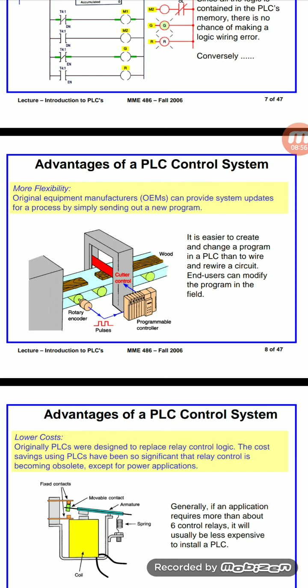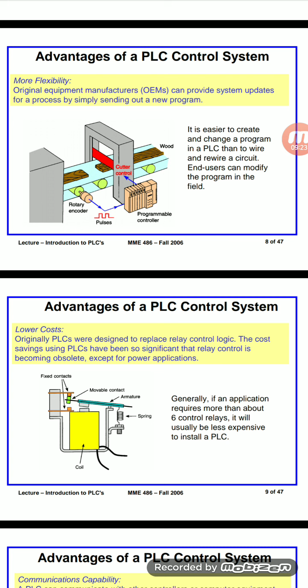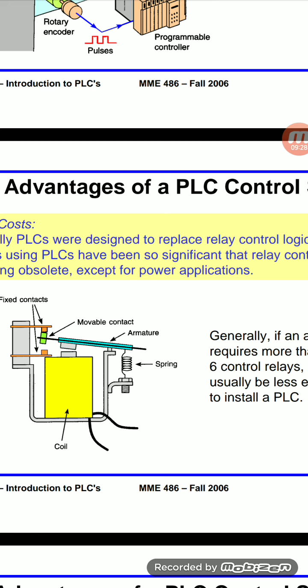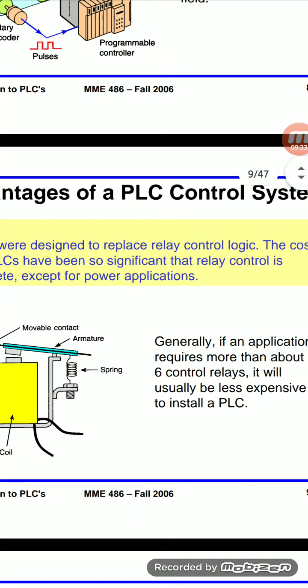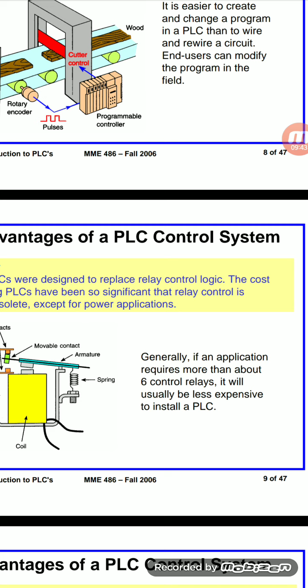Next, lower cost. Originally PLCs were designed to replace relay control logic. The cost savings using PLCs have been so significant that relay control is becoming obsolete except for power applications. Relays have a movable armature, spring and coil. Generally, if an application requires more than about six control relays, it will usually be less expensive to install a PLC.